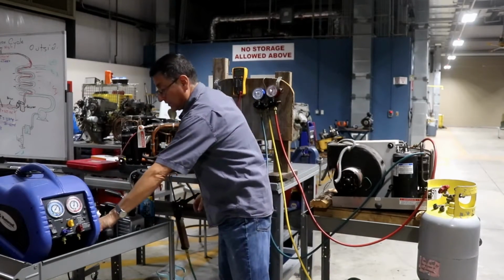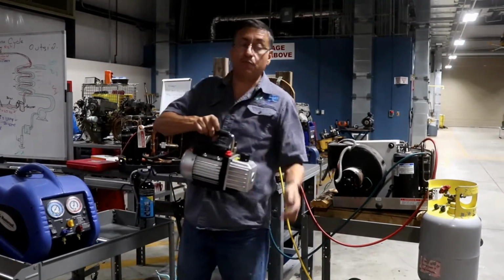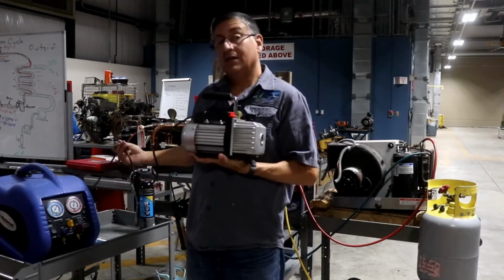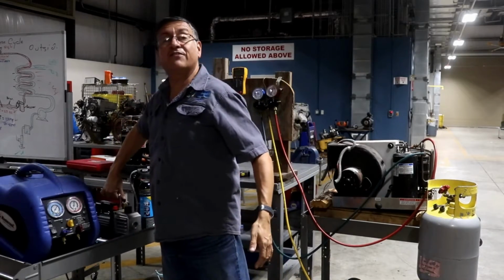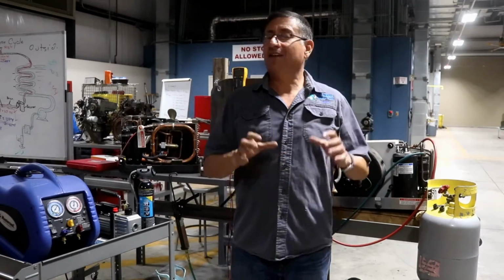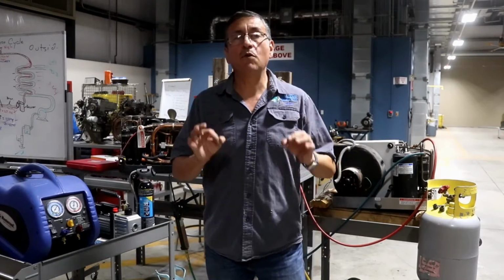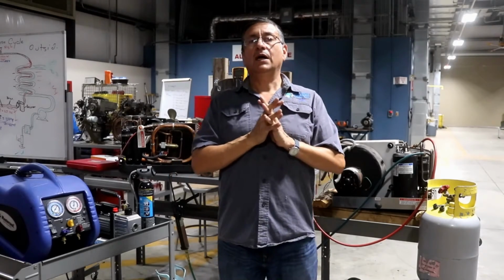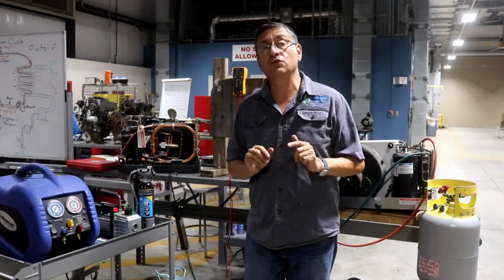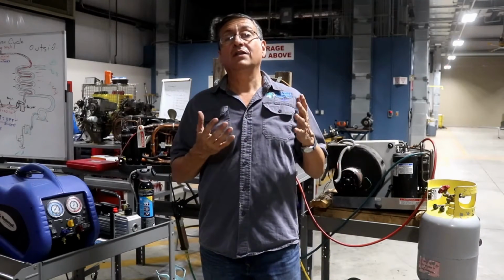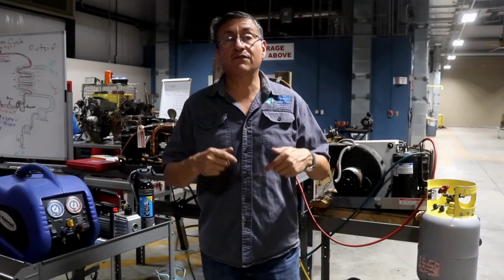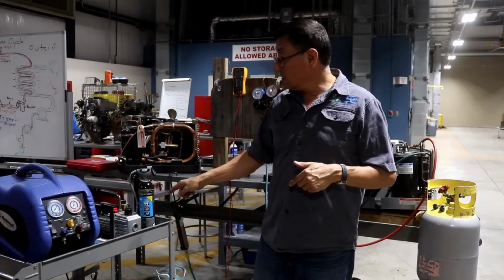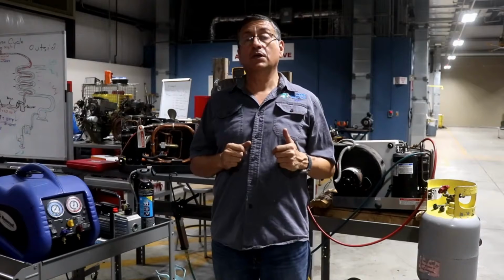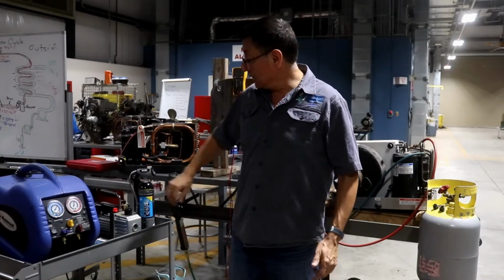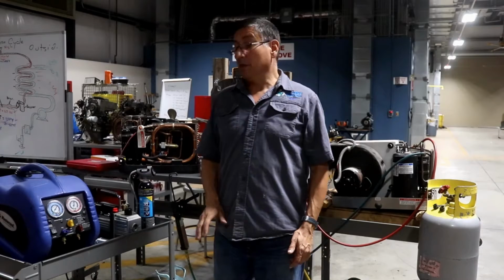Those tools are important. We are going to use the vacuum pump. The vacuum pump is important when you recover the refrigerant. We are going to use the vacuum pump to remove moisture. The function of the vacuum pump is to remove moisture. ABYC question. And yes, I am going to explain the procedure to use the vacuum pump and how to service it. You need to replace the oil in the vacuum pump and verify the level of the oil. This is very simple, the vacuum pump.